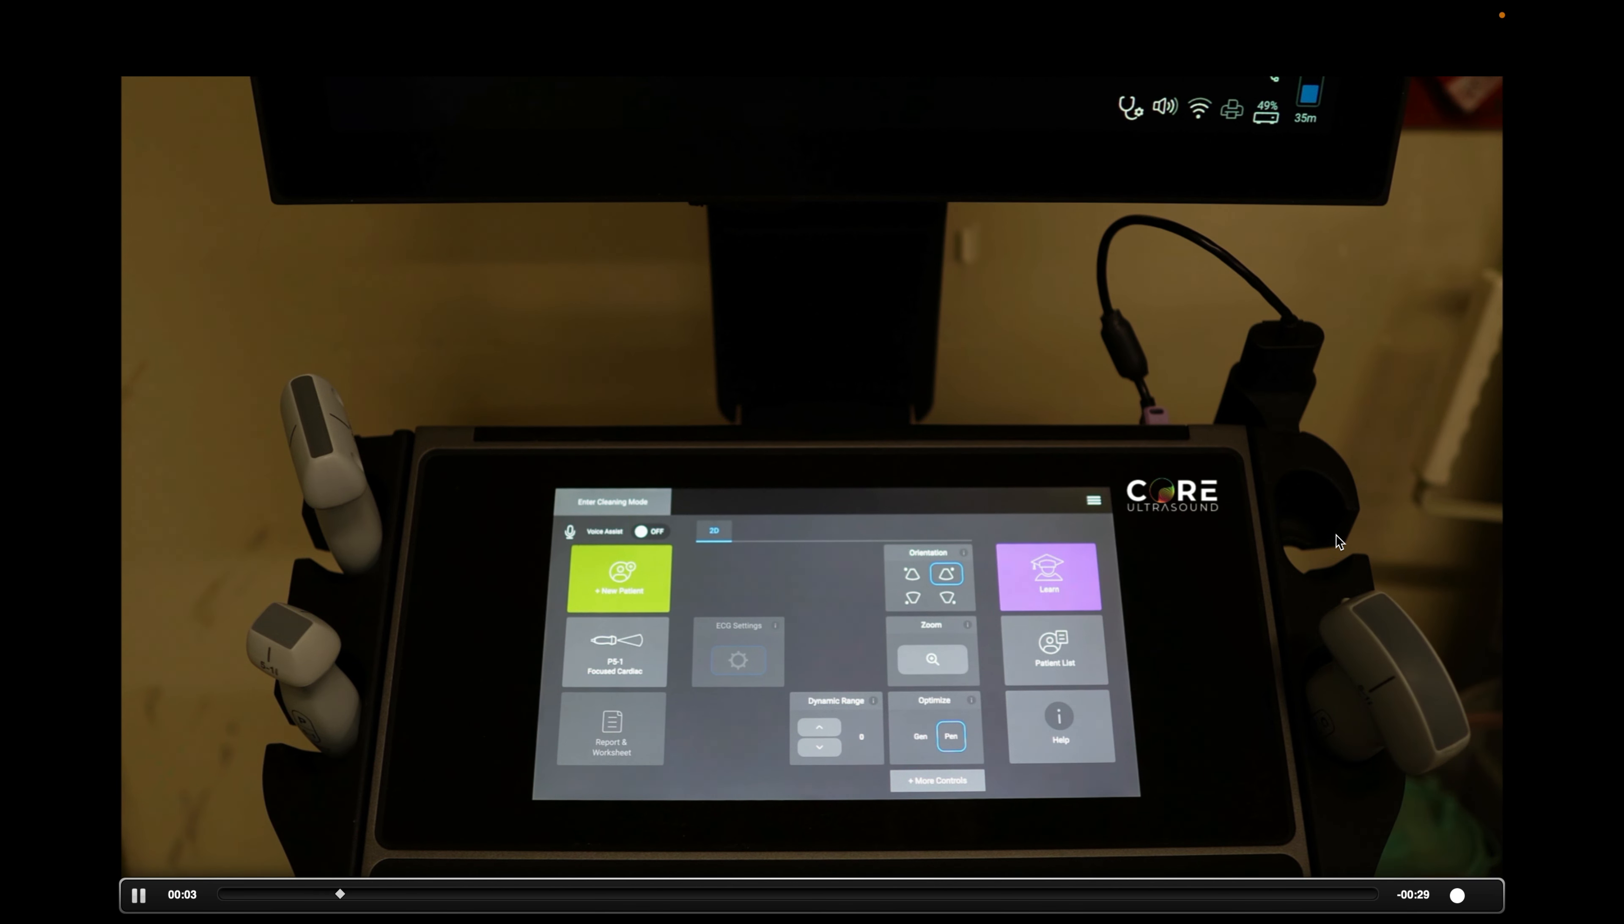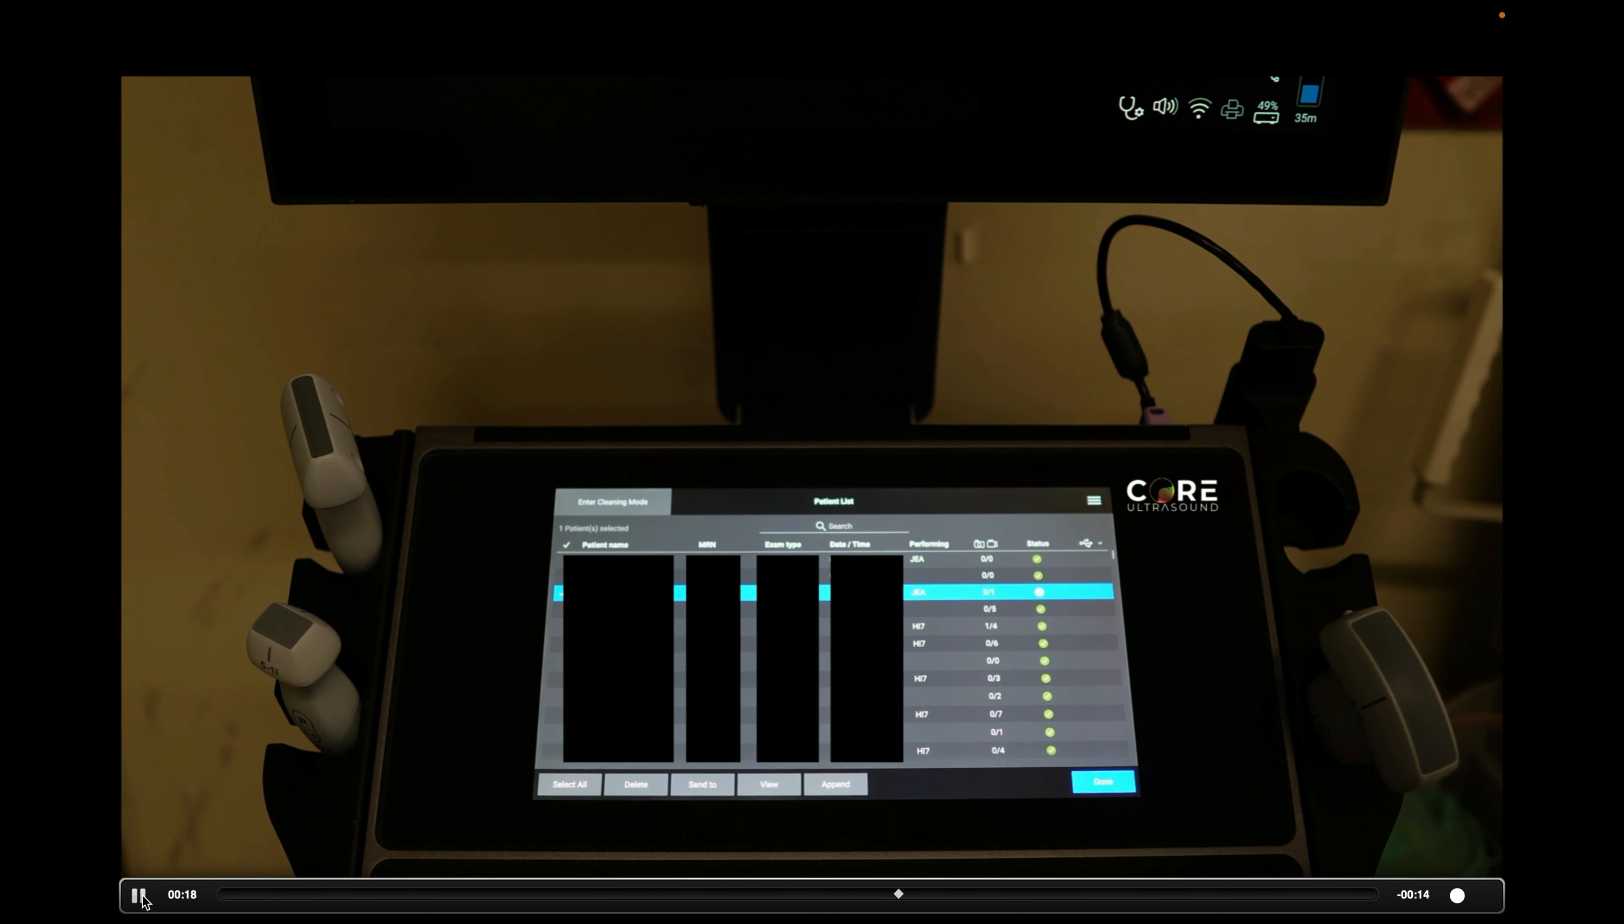You have a couple extra USB ports over here. This is a microphone for voice commands if you happen to want to use that. And when you have that plugged in, you can export. So the way that we do that is we're going to go to the patient list button on that right side. You are going to select whichever study you actually want to export, which I chose that one. And then you're going to hit the send to button on that bottom and then click USB. Make sure that you have your USB drive selected. You can decide if you want to include patient information on there or not, and then hit send and it will start to transfer. And if you look up here, you can see these three dots that are kind of moving. This is the machine saying that it heard you and it is currently working on transporting your clips to that USB drive. And then when you're done, just hit the done button.